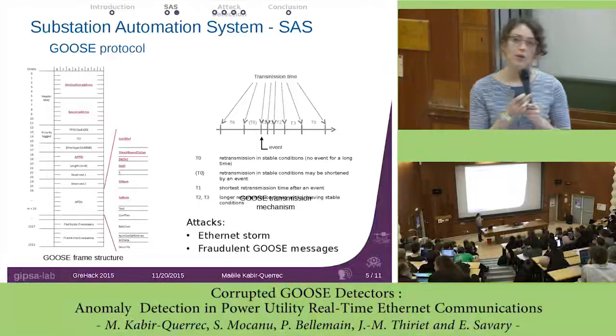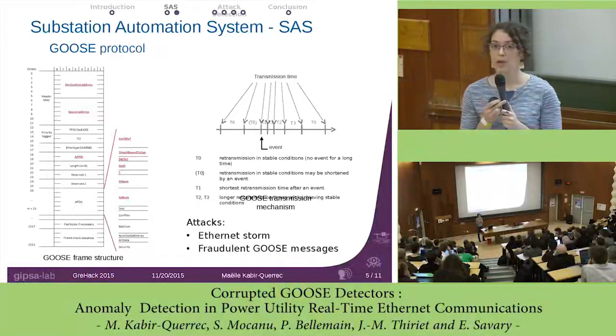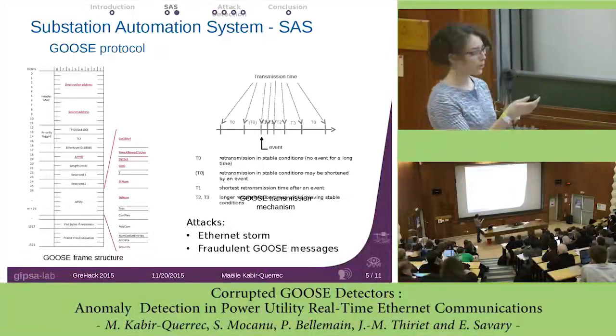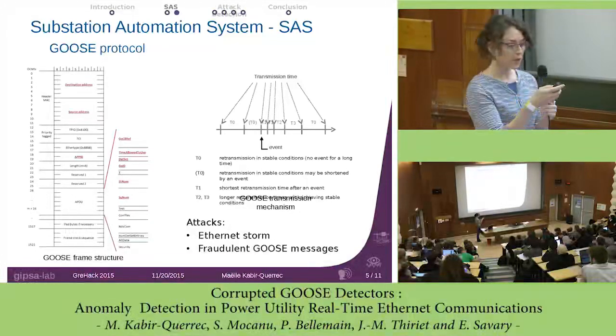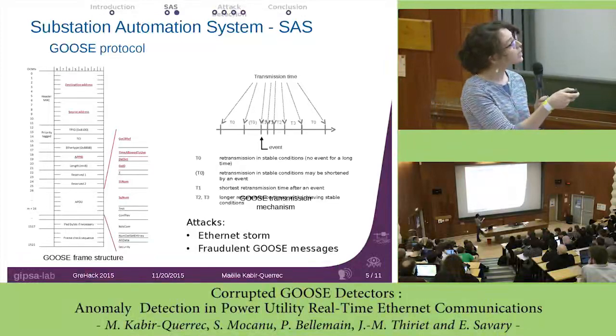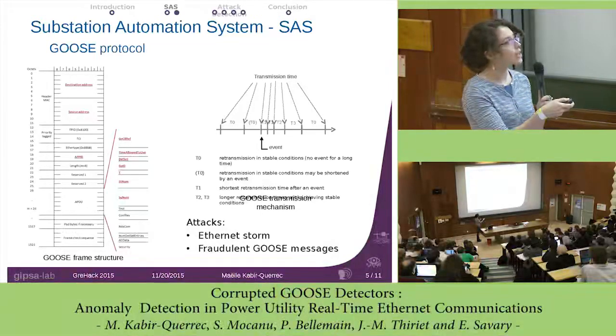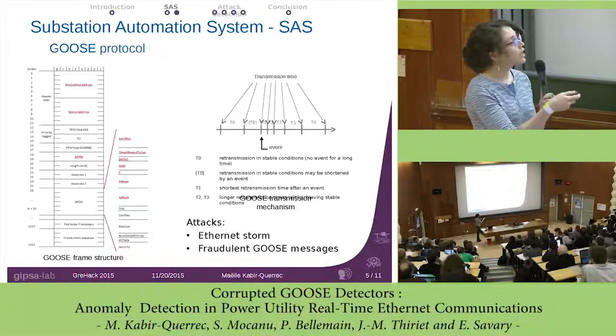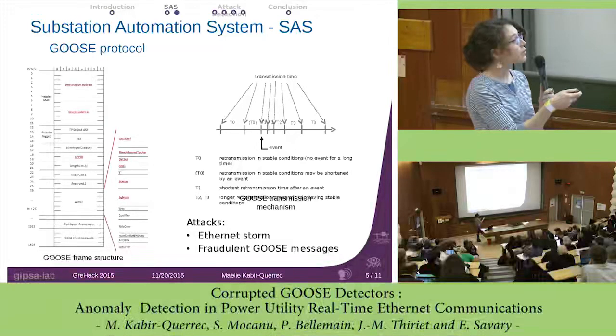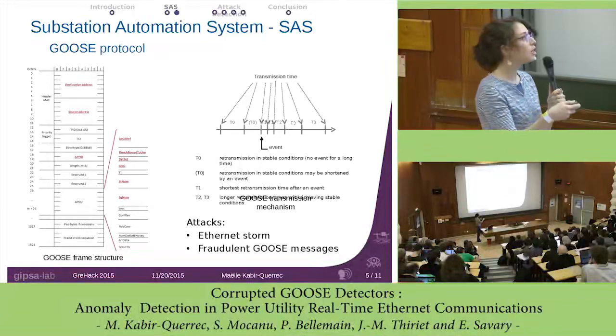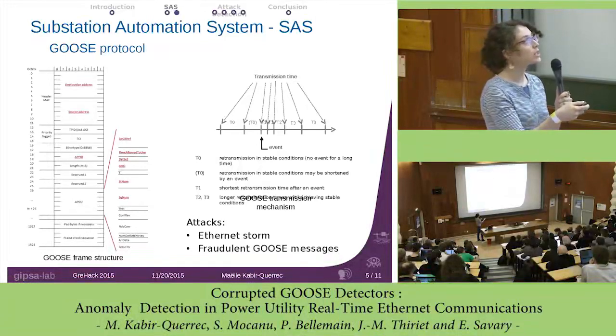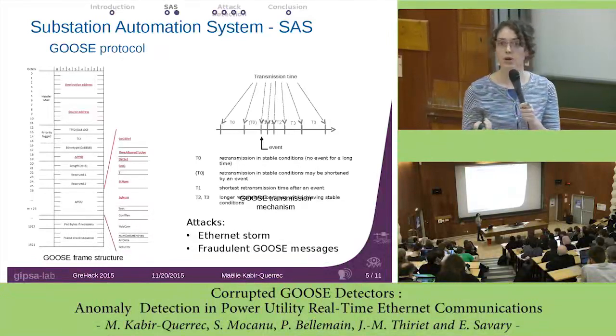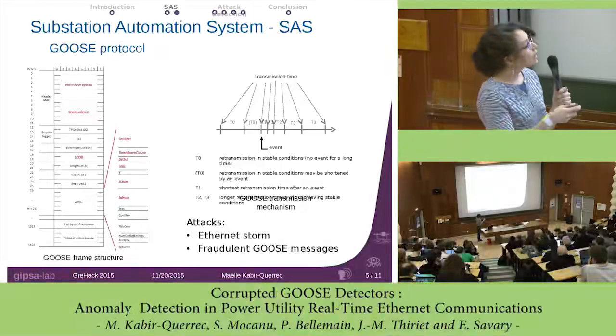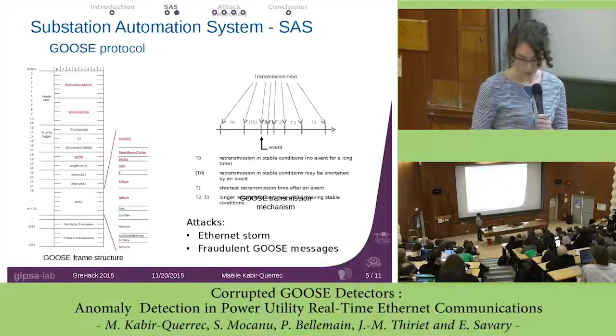So, as I mentioned, GOOSE is a multicast protocol. It means that there is no acknowledgement of reception. To make this protocol a bit more reliable, there is a specific transmission mechanism. When you have a data value change, there will be a new GOOSE message sent here. This is what I call an event. Basically, it's the change of variable value. So we have a GOOSE sent here. First, it will be sent at a very high frequency, T1, and then we divide this frequency by 2, and so we go at a slower pace, T2 and then T3, until we reach stable conditions and have a normal pace of frequency T0. Those frequencies depend on your devices and can be configured. Okay, so that's it for that.